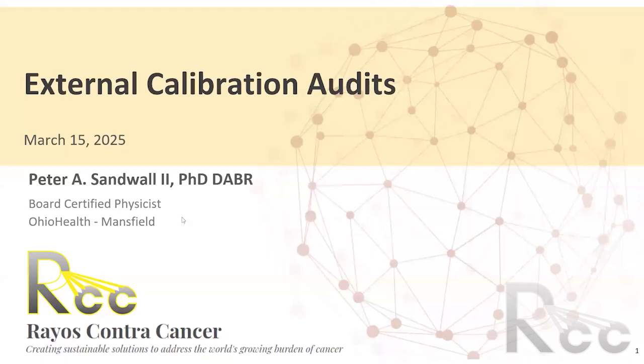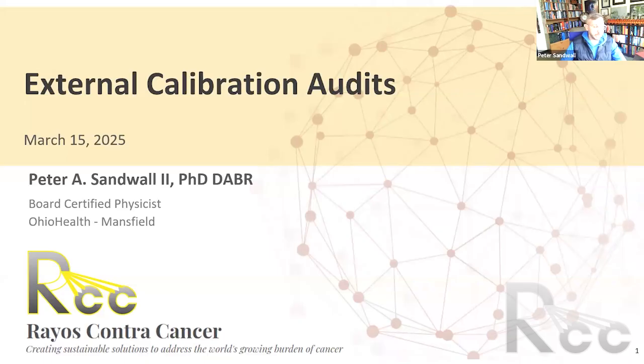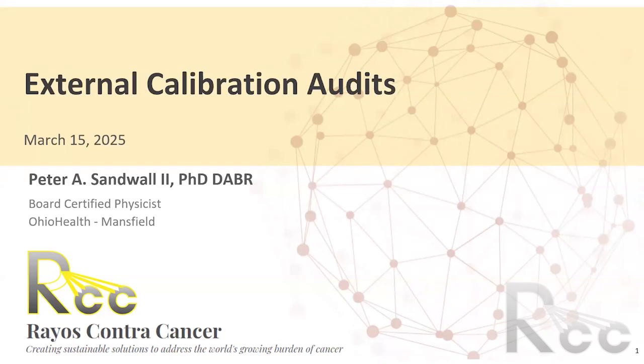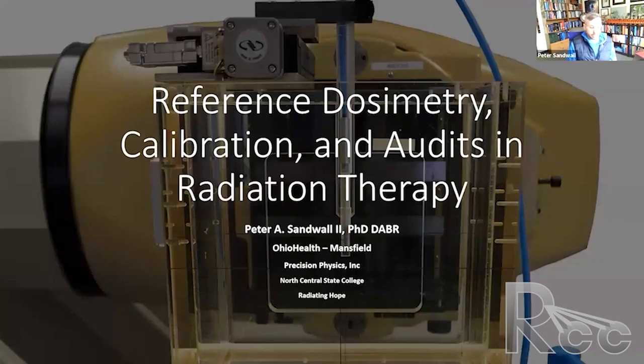And one of the things that we do that is unique, maybe not, perhaps not unique, but was something that I had not experienced elsewhere, is that when we calibrate, we always calibrate with two physicists. It as visits from outside accrediting bodies, or they can be postal dosimetry audits, where we irradiate a dosimeter that we send back to a third-party lab that checks our calibrations. And this is all in the context of radiation therapy. And we have here a farmer chamber being irradiated by a cobalt unit.